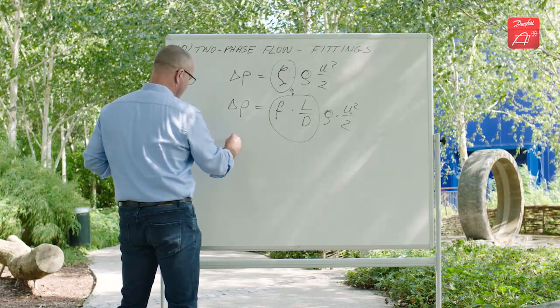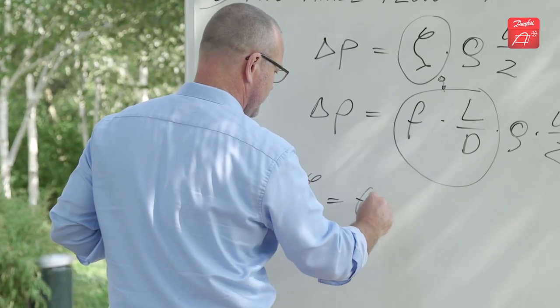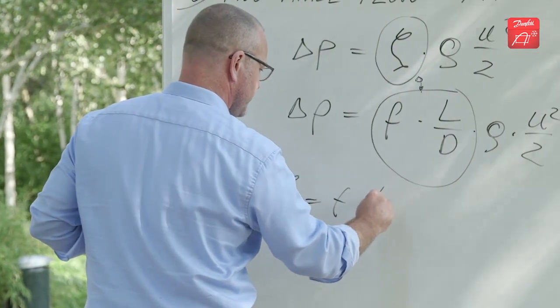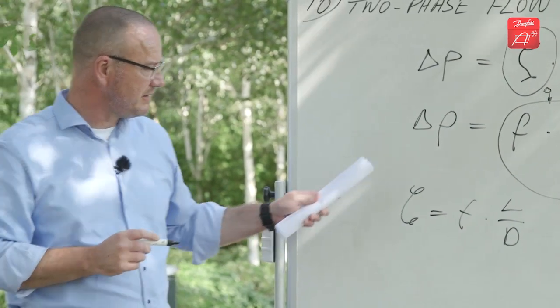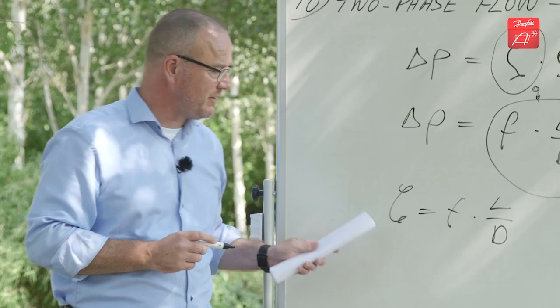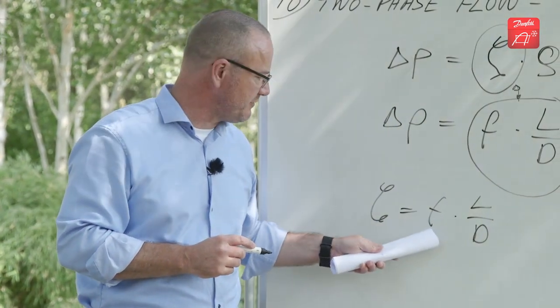So if we write that the resistance coefficient is equal to a friction factor times L over D, it actually means that to calculate a fitting you could as well calculate a pipe with a friction factor F.